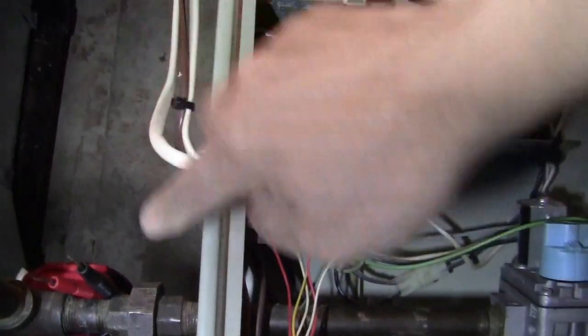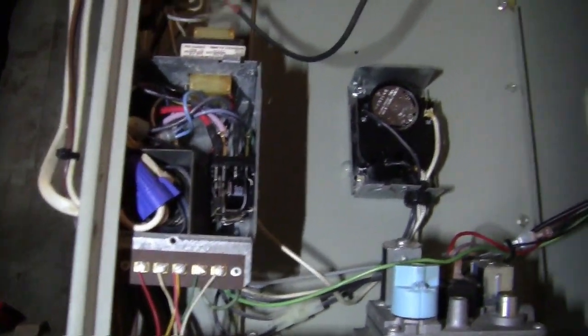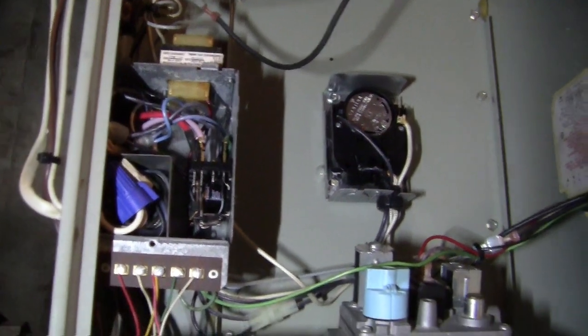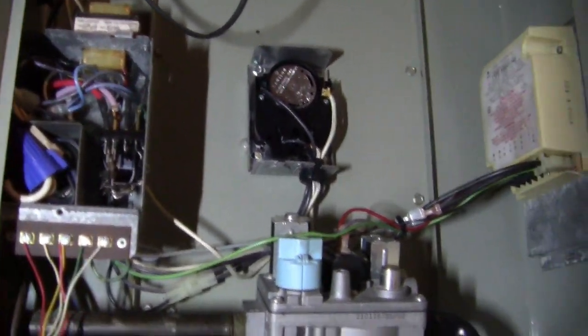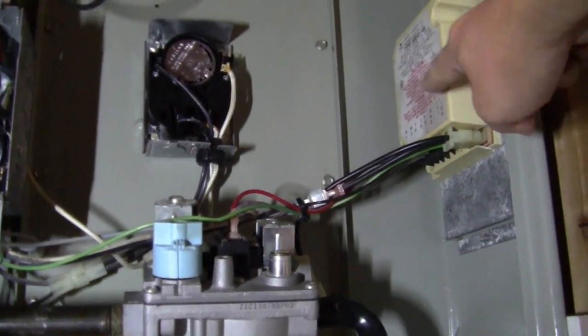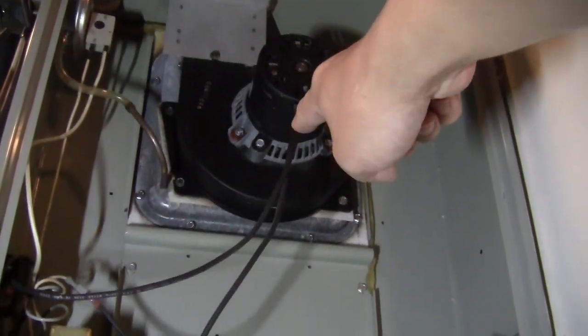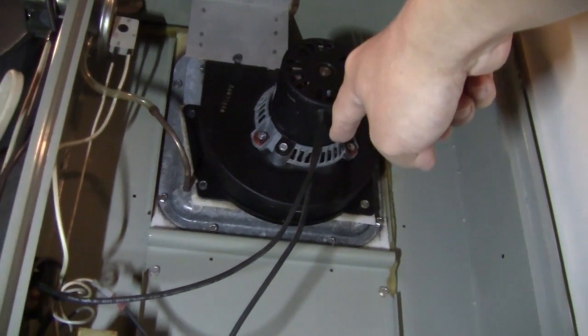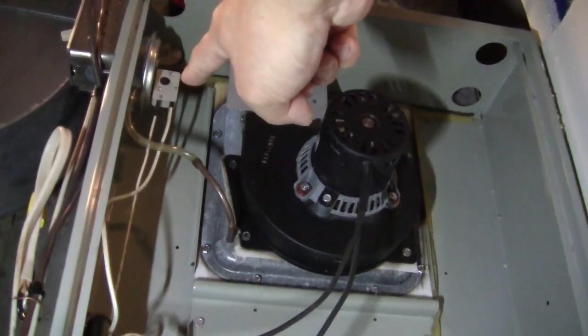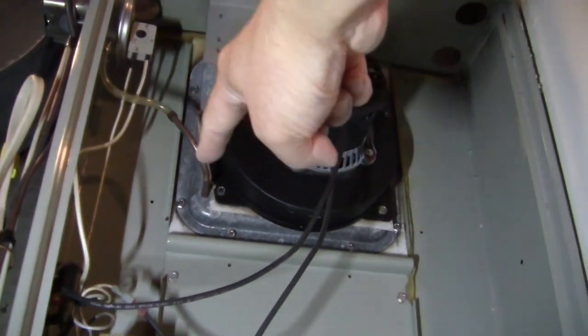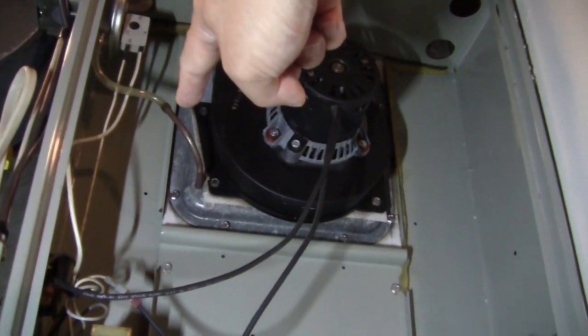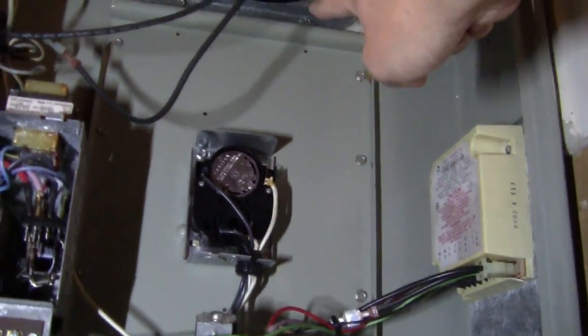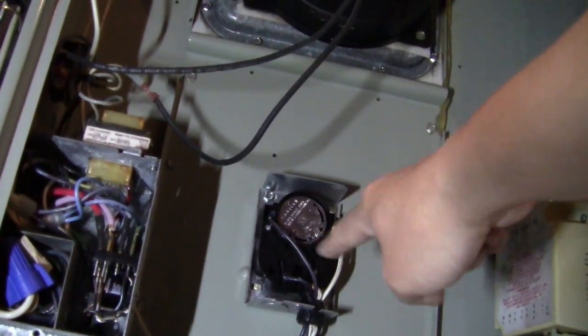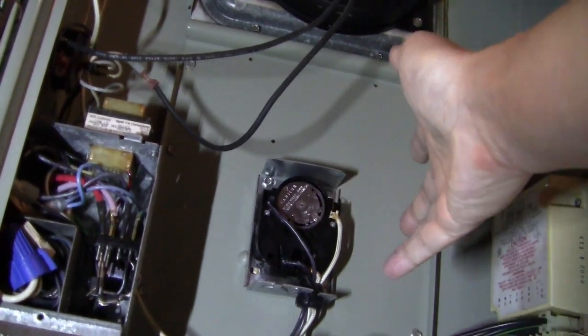On the top, you see this wire. This is the signal wire from the control panel to here. I set my temperature higher than my room temperature. So if I turn on the power switch, it's supposed to kick in the signal to this controller. And this controller, first of all, is going to turn on the fan over there. The fan is going to run. After the fan runs, you're going to have the vacuum sensor detect the vacuum in this wire and this tube, and then send the signal to the controller. The controller detects the fan is on, right? And it also makes sure this controller is initialized. It has no problem at all because there's no higher temperature inside.